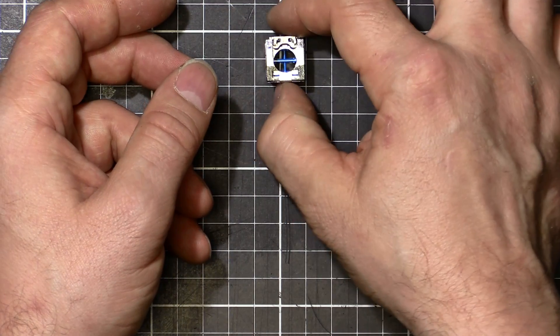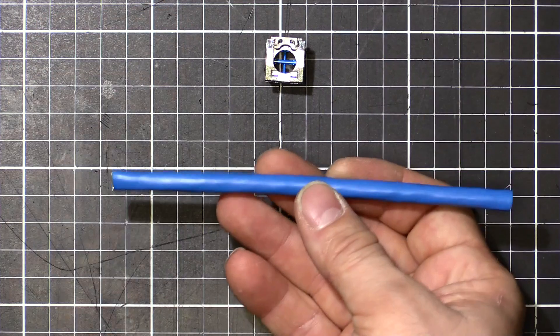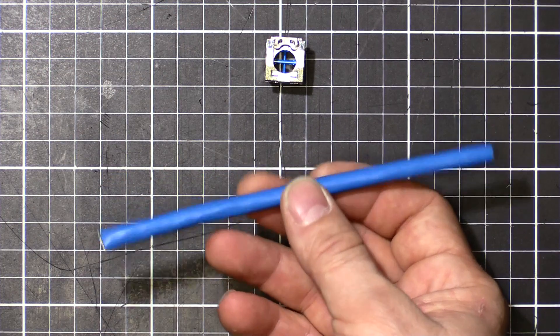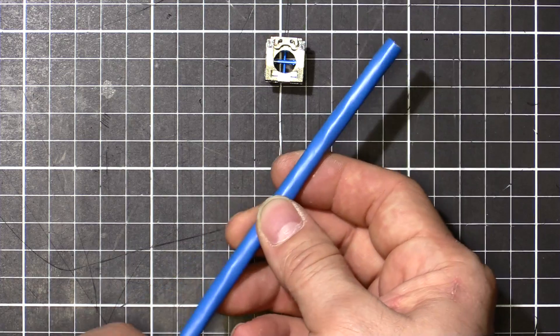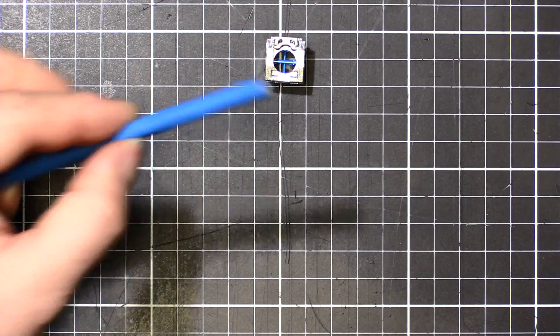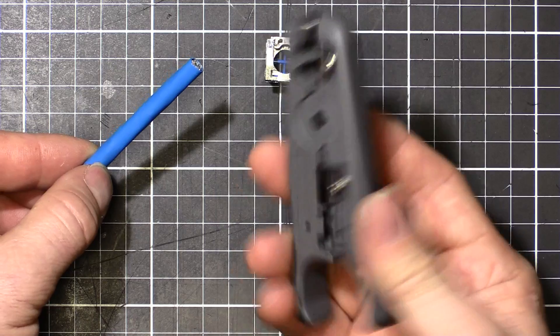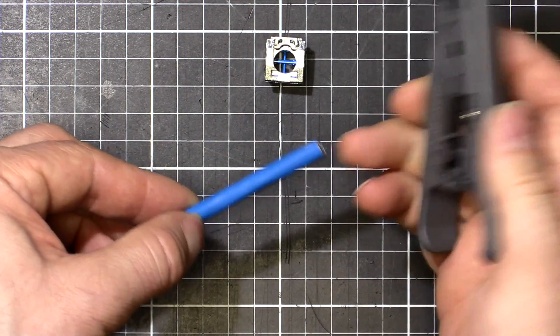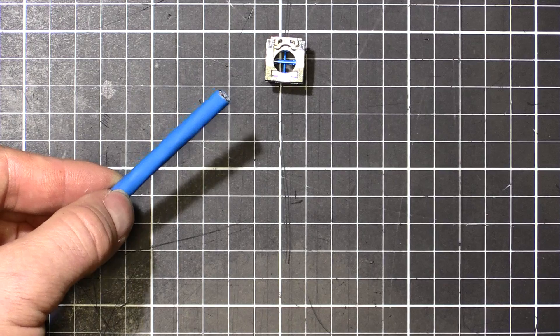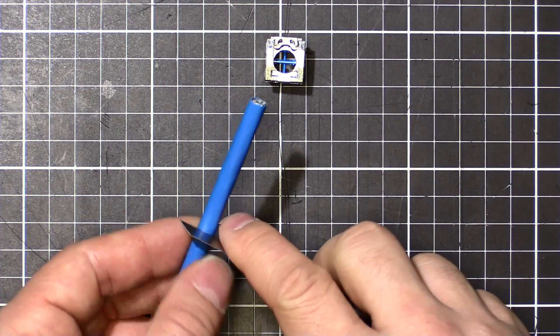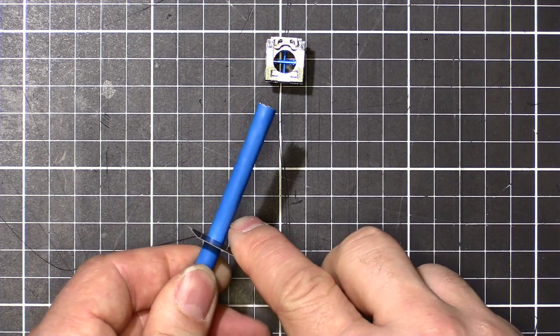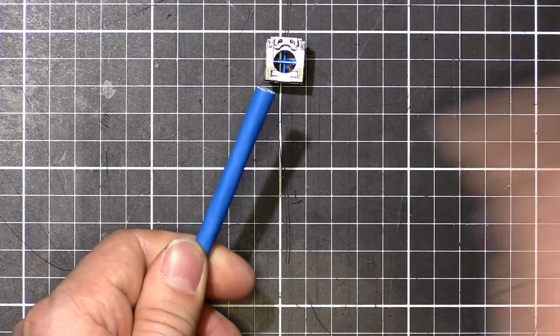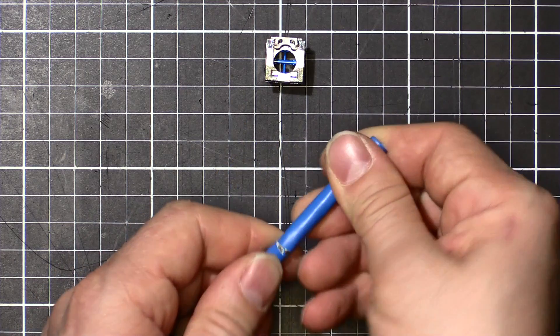We'll put that aside because now we're going to strip our cable. I'm just going to use a small, short bit of cable for the demonstration. We have to strip back 50 millimeters. Now like I said, the capacity of my strippers is too small, it's going to cut into the conductors, so I'll be using my knife. I've just got to score that carefully so I don't go through and cut the shield.